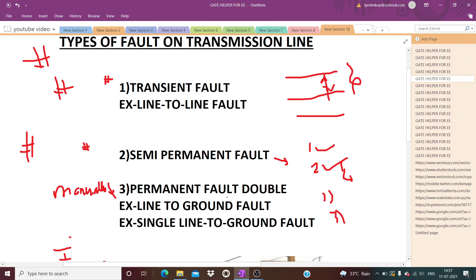In the third step, the circuit breaker gives clear information on whether it is a permanent fault or not, so the substation people can take action accordingly. If there is a permanent fault, they will not send power to that region and will manually come and correct it. But if it is a transient or semi-permanent fault, they will restore the power.